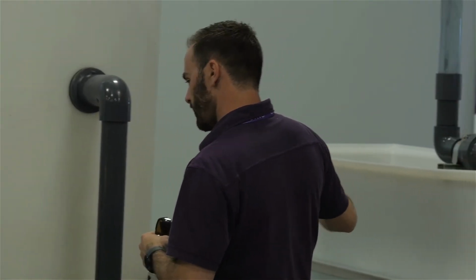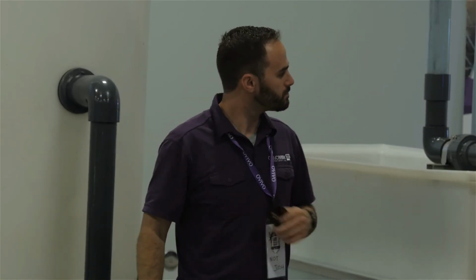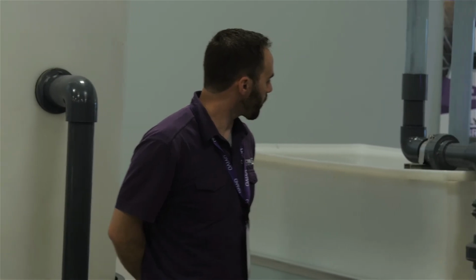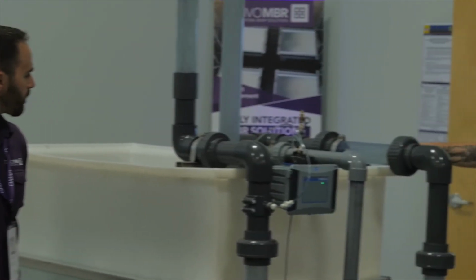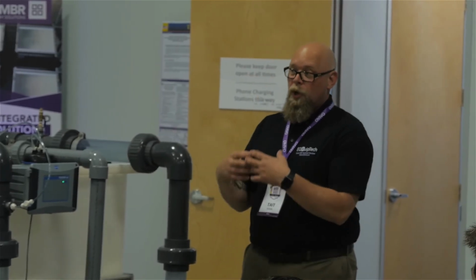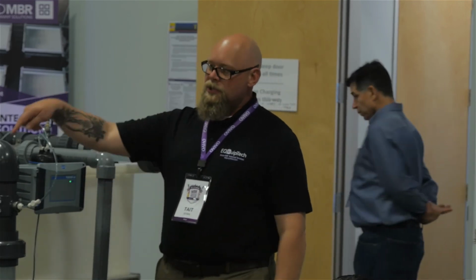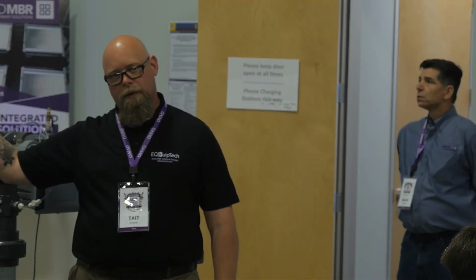Kind of hydraulically, the cumulative effect of what's going on is that when this pipe is full, a third of this pipe is being taken up by an air bubble. So the consequence is the pump's got to work harder to pull the same flow through a smaller pipe. And in addition to air bubbles messing with the magmeter's ability to read accurately, that pump is choking on air as well. So this sort of accumulation of error just has things going all over the place.